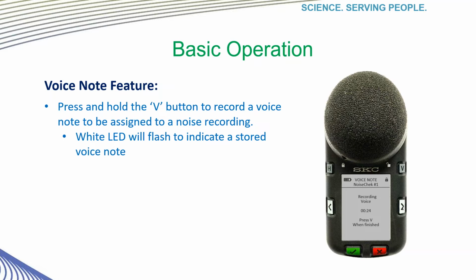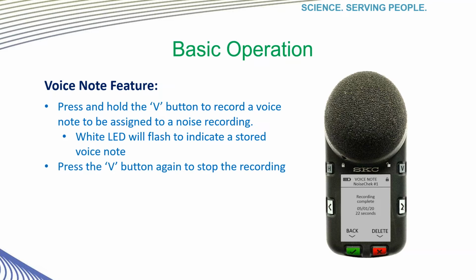Anytime after calibration, before you start the run, if you wish to make a voice note, you just press and hold the V button, or voice record button, to record a new note. A white LED will flash indicating a new note is being recorded. When you have completed your message, press the V button again to stop the recording. This message will be saved to the data logging and retrievable from your report. The white LED will now flash at a slower pace just to let you know that there was a message stored.